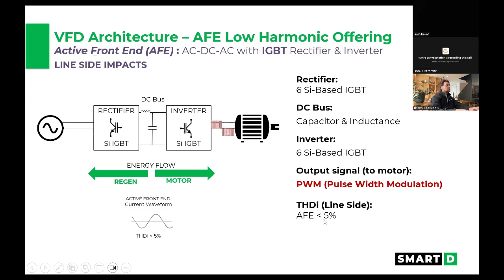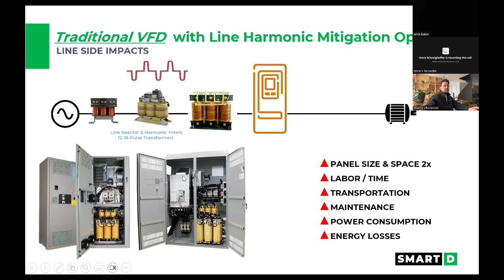So we have a rectifier, we have a DC bus still, which is awesome because then we don't have any voltage drop issues. We'll get to that in a bit. And of course, on the inverter side, it's still an IGBT-based inverter side, but you can get your harmonic distortion down to less than 5%, and you get to reduce your footprint. So let me just go back here. If you've got an active front end here, you can knock out the active harmonic filter, one of these guys. All of these guys are gone if you've got an active front end. So that helps reduce your footprint.